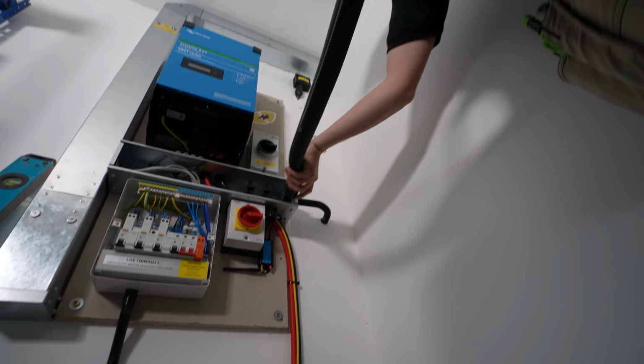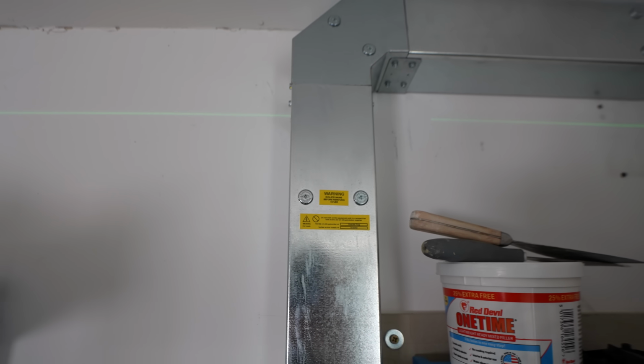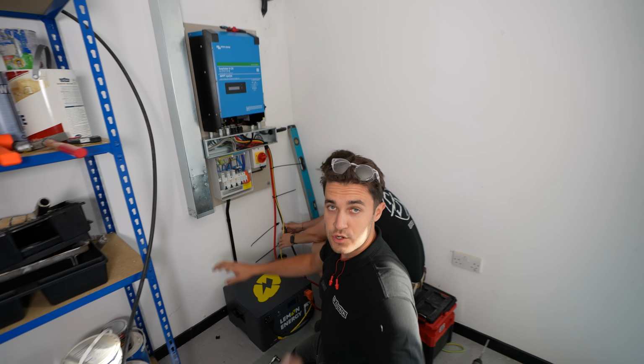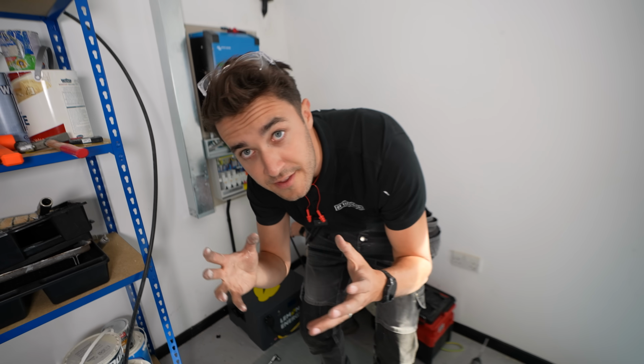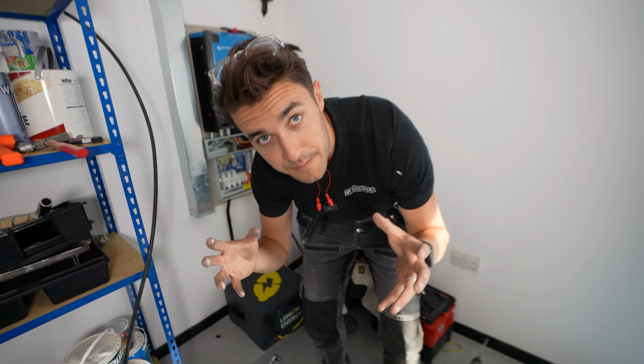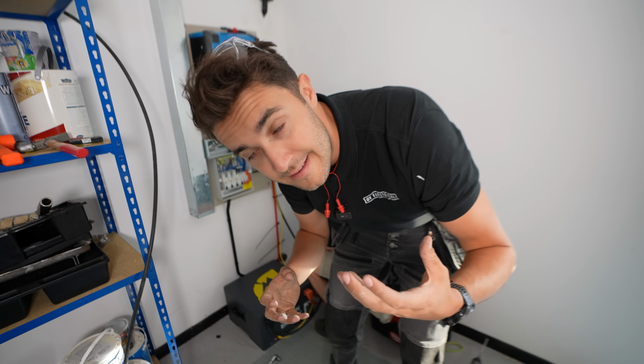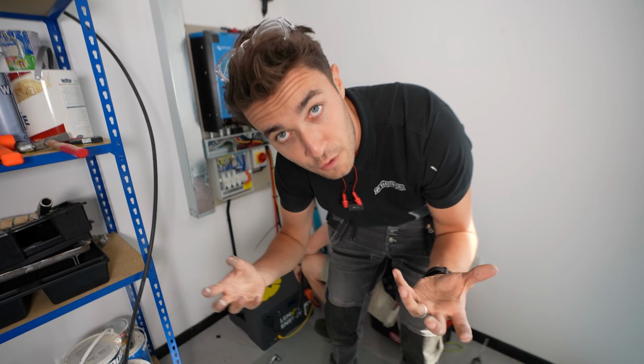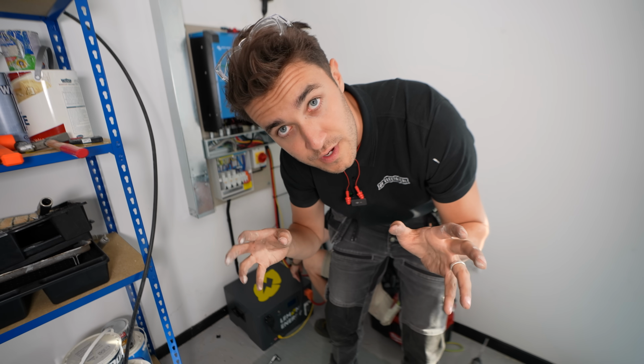Now that the battery's in and everything is all labeled and lidded up, it's time to start up and commission. The startup procedure for Victron is very important, okay guys? As it's more of a commercial grade system, it's not going to be as friendly and cuddly as something like an Anker when you switch it on. If you get it wrong, you do risk breaking stuff.